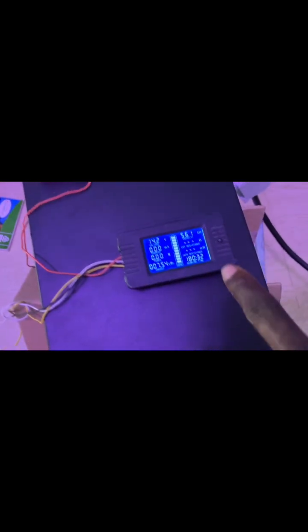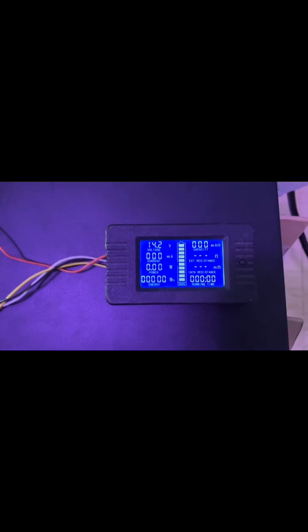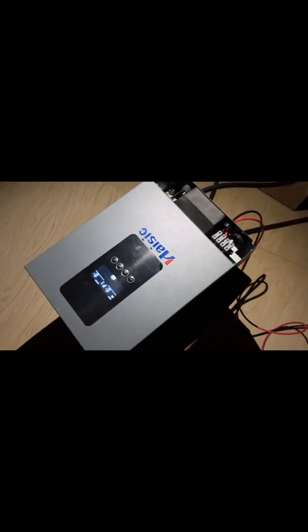The battery is full now, so we are going to reset this capacity to zero. Clear. You can see everything is zero now, so the i6 inverter is the one that will take over now, and we'll start the test.